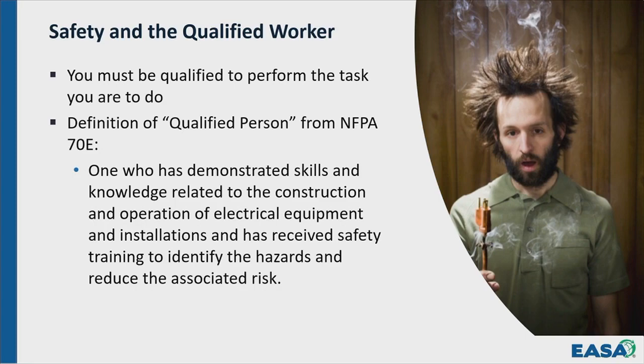A 480 volt motor control center could do a lot of damage to you and equipment around you based on fault current and incident energy. I was involved in a 400 amp, 480 volt automatic transfer switch failure in 1984. It blew up in my face, put me in the hospital for a week and a half, and off work for a month, because I did something wrong. It was just 480 volts - not that big a deal, but it is a big deal. It's a big deal at 480 volts, at 240 volts, at 2300, 4160, 13.8, whatever.